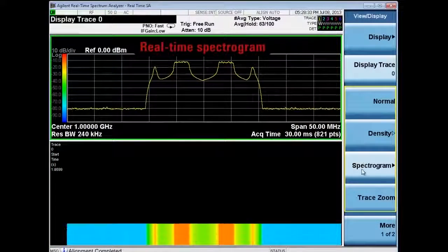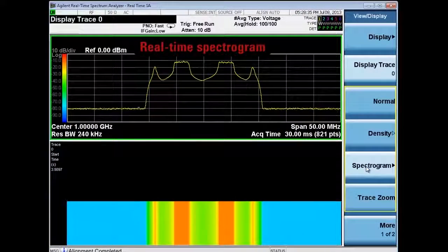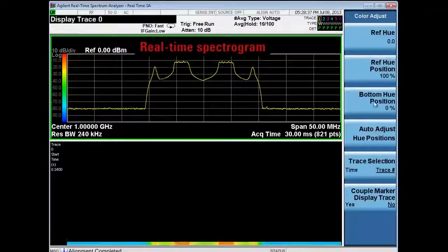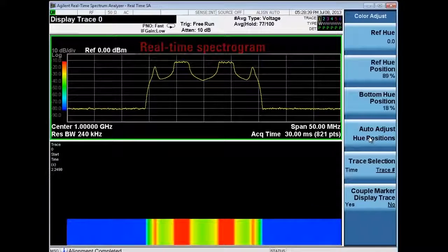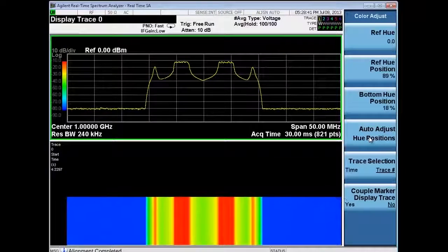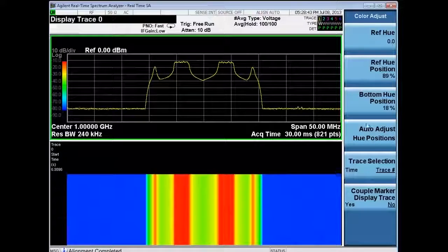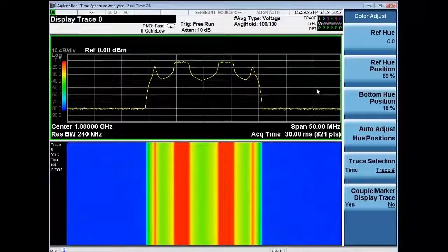In the MXA's real-time mode, we are processing the gap-free time domain samples very fast, almost 300,000 FFTs per second. This allows us to see the entire bandwidth without gaps, so we see all the transient activity and don't miss elements of the signal.